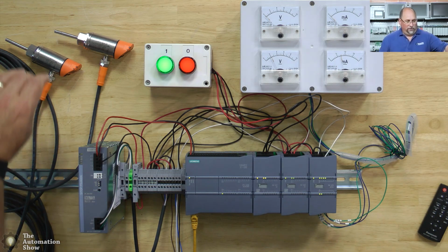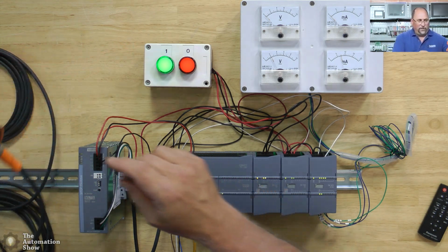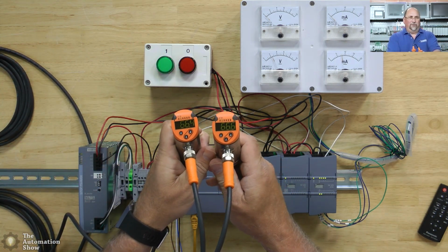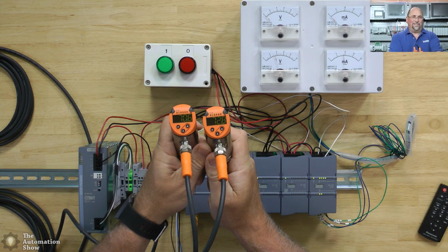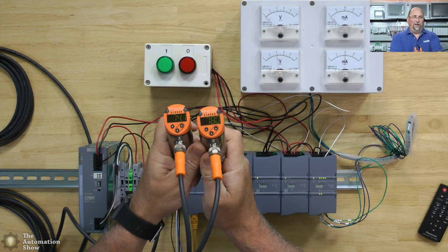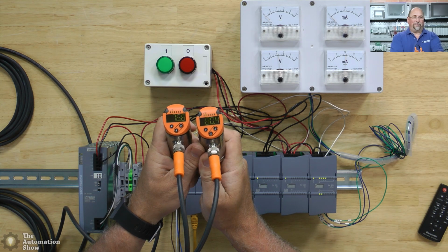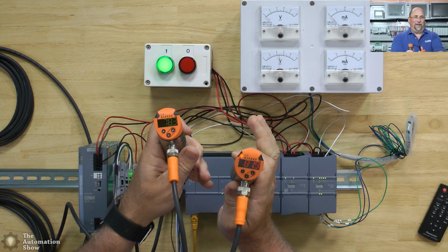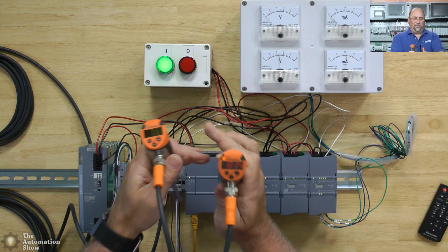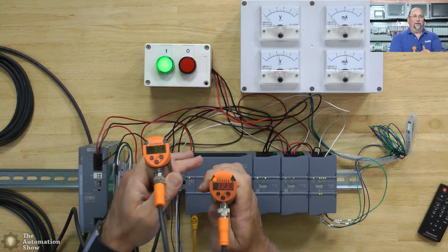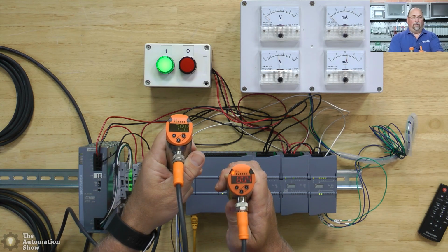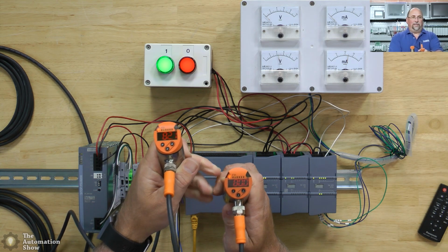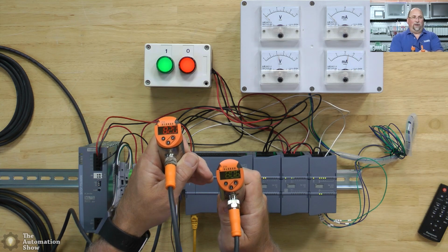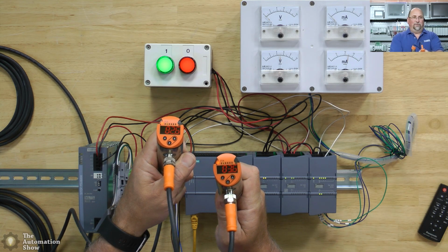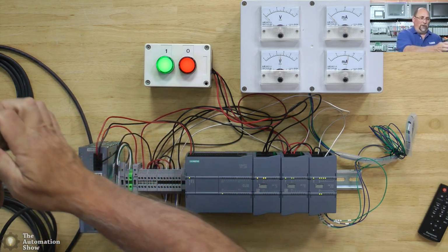Okay, and what I'm going to do is, you can see I really got the temperature down in here this morning. Okay, now you can see they're going. They were like at 64. So now they're climbing. Oops, this one went to 80. That one's still at 78. So you can see I got one output. And if I bring the other one over 80, I get the other output. Oh, this one already dropped down below 80. Okay, so I'll warm them up both quite a bit over 80. And I got both my outputs.